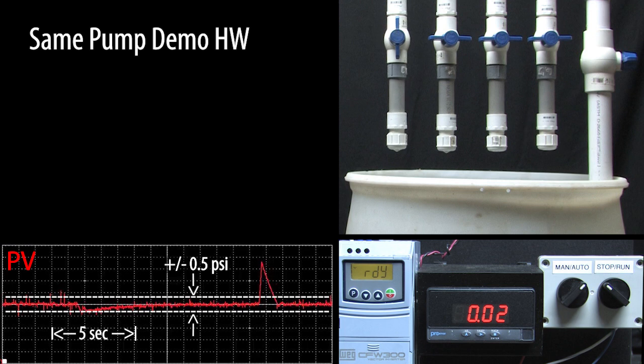So if the pressure drops because we ran out of water in the reservoir or a pipe breaks or a sensor shorts to ground for longer than 5 seconds, the drive won't burn up the motor or the pump trying to get the pressure back up. And if the sensor faults with the signal indicating high pressure for more than 5 seconds it will also shut down the drive.